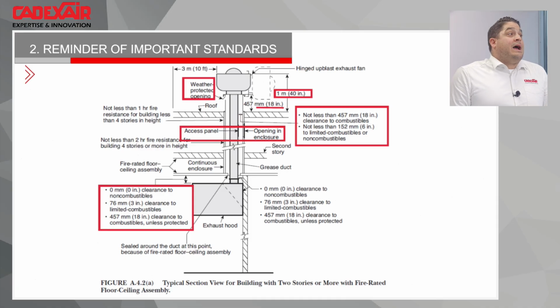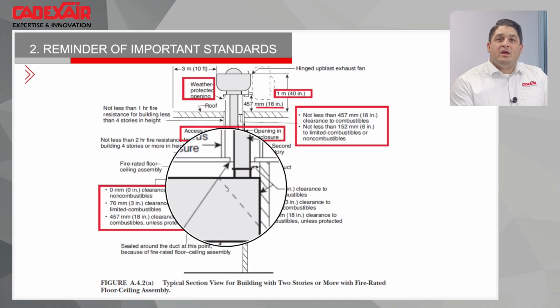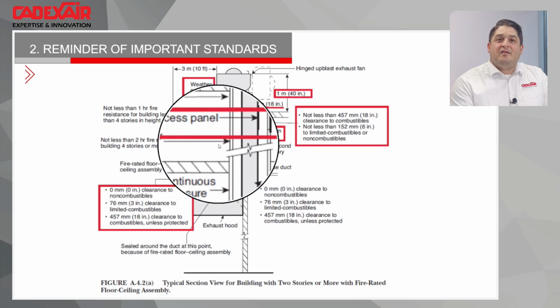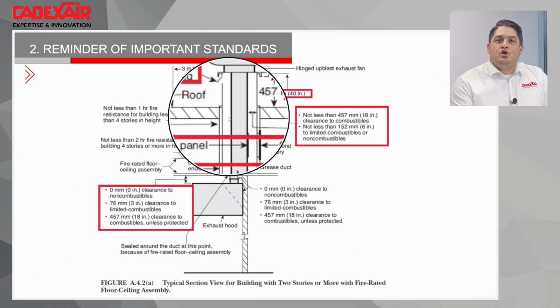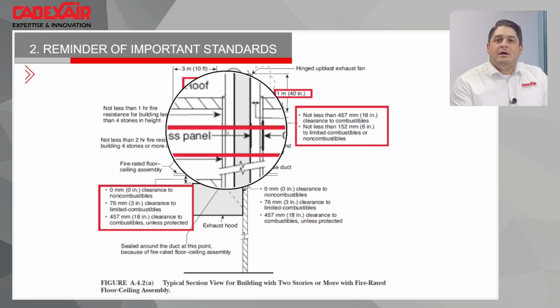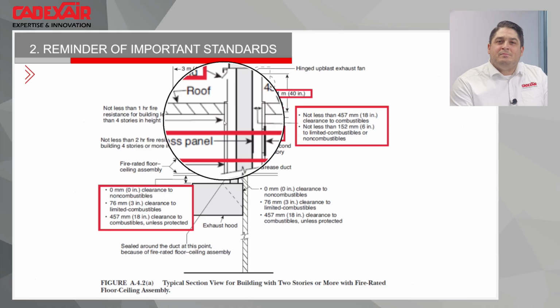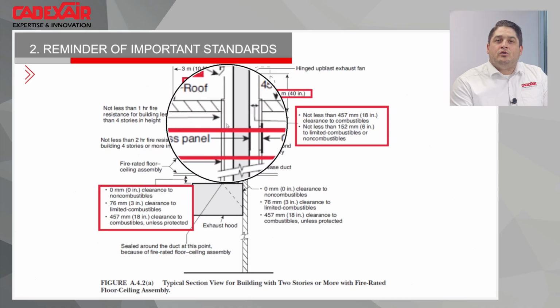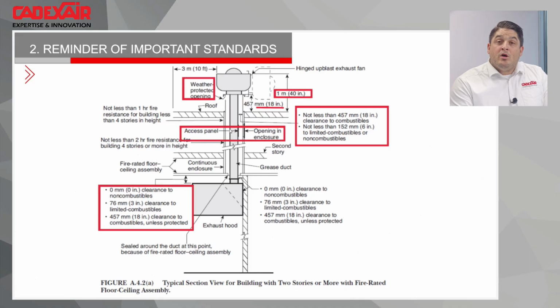So how can I exit my fire zone without creating more problems? In fact, the mechanical shaft's purpose is to create another layer. Right there, that is the shaft that will go up to the outside. And technically, if you are between the shaft and the fire-rated assembly, you're in the same fire zone as the hood. Maybe it's not, but that's the way to understand it. It's an extension of the fire zone of the kitchen up to outdoors. So there's a thing here.